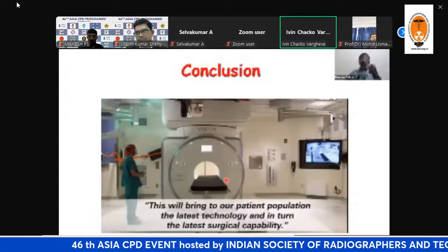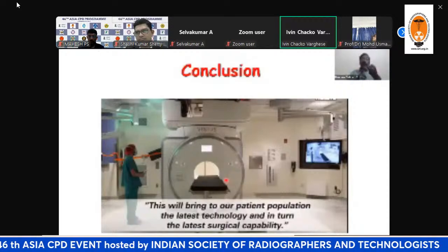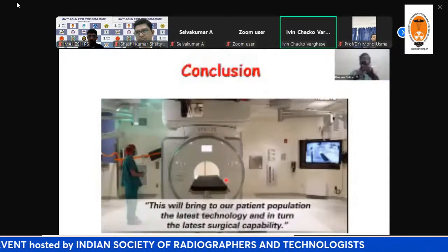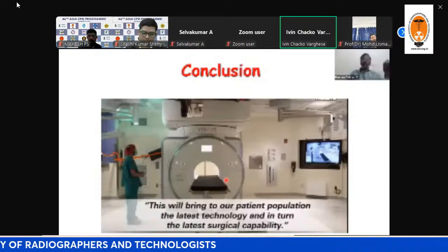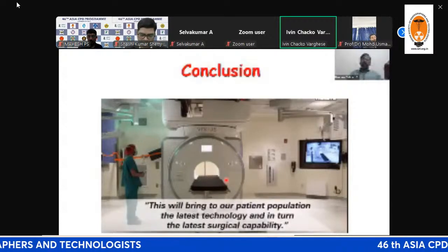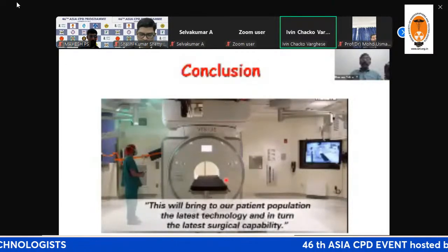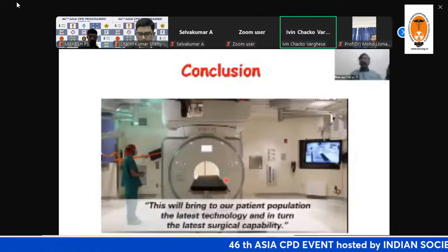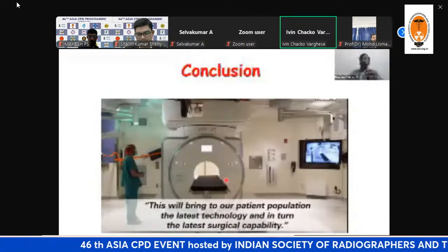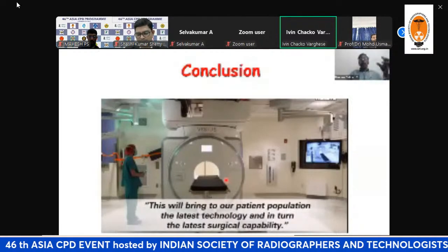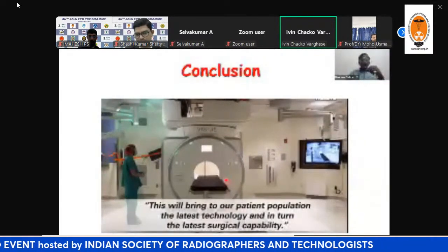First, I explained to you what is IMRI. Then I told you the two different configurations. In the first configuration, the patient will be shifted to the MR room, which is located adjacent to the operation theater. In the second configuration, the MR equipment can be shifted to the operation room, but it is expensive, and it is going to be moved by a ceiling mounted system.